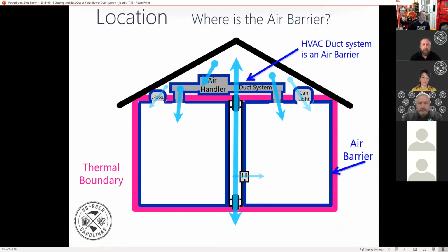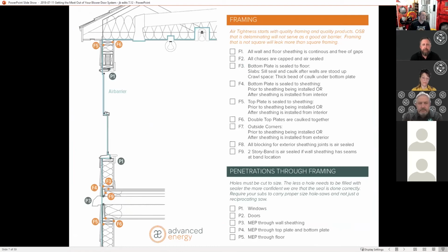But these are some drawings here that we put together. I used to work for a company called Advanced Energy in Raleigh, North Carolina, and we put together a checklist for builders to show what are some common areas where you want to pay attention to air sealing. If you're looking at the wall itself, you're looking at this teal line here, and anytime this line moves is a potential to have an air leak. Anywhere there's a corner, or anytime one material changes to another material, that's an important area to consider to make sure that's going to be a tight assembly.